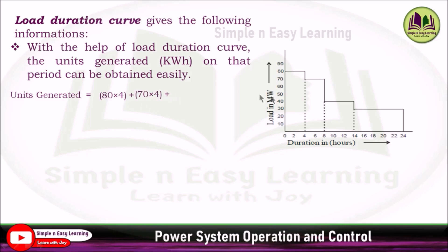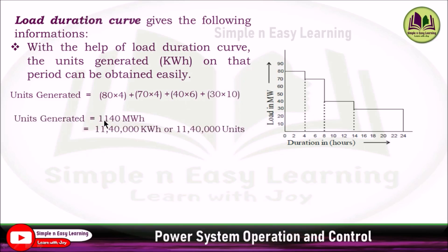So: 70 × 4, plus 40 megawatt which lies between 8 AM to 2 PM — that is 6 hours, giving 40 × 6 — plus from 2 o'clock to midnight, a total of 10 hours at 30 megawatt, giving 30 × 10. Adding these together gives total units generated as 1,140 megawatt-hours. Converting to kilowatt-hours, that is 11,40,000 kilowatt-hours — that is 11,40,000 units for this particular load duration curve.